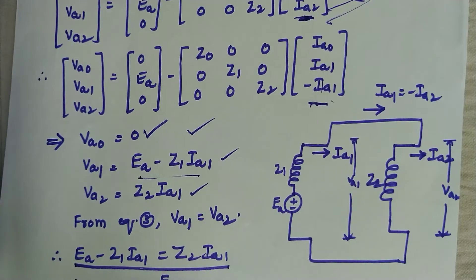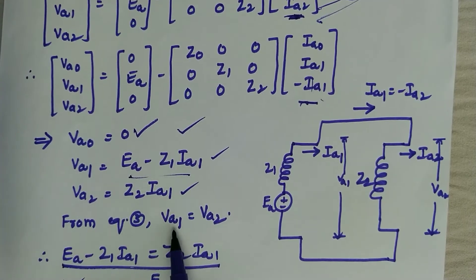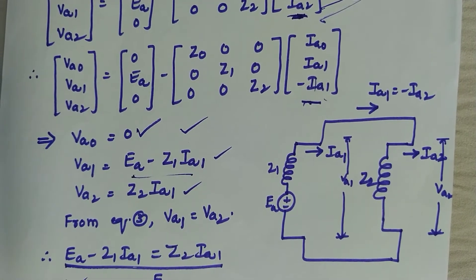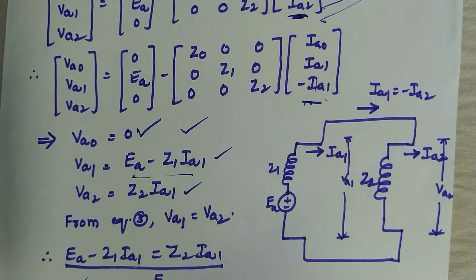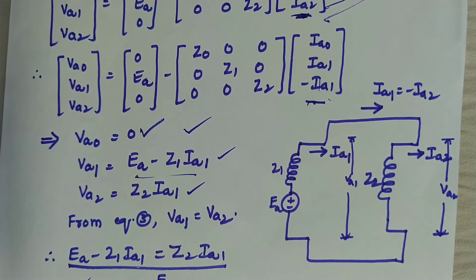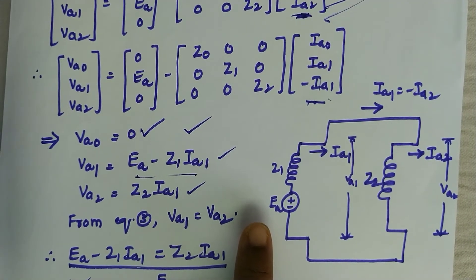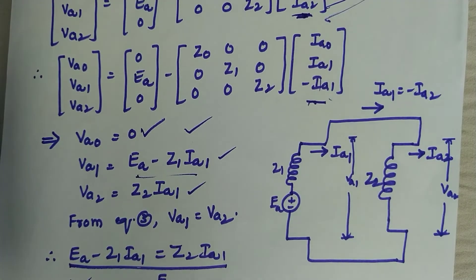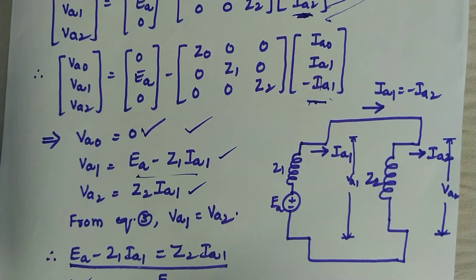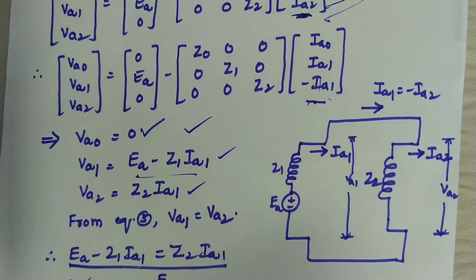Since Va1 equals Va2, the positive and negative sequence networks of the generator must be connected in parallel. Since Va0 is 0, the zero sequence network is shorted and need not be considered. Since this fault does not involve any ground connection, the neutral current is 0, and hence the presence or absence of a grounded neutral at the generator does not affect the fault current.